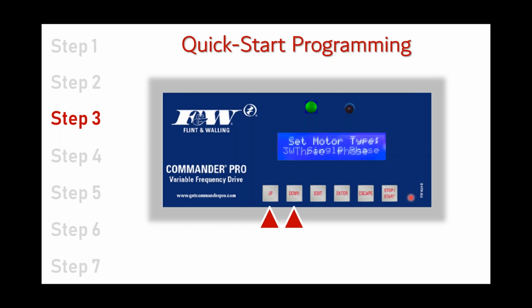But anyway, for purposes of display, we'll go ahead and select the 3-phase motor. We hit enter. We know what that does. That saves it. So where are we at? We're 2 menus in, so we go to the third menu. Here's where it's going to ask you to set the max motor current, or the max motor amps. And again, this is how we're going to display what horsepower motor this drive is expected to operate.